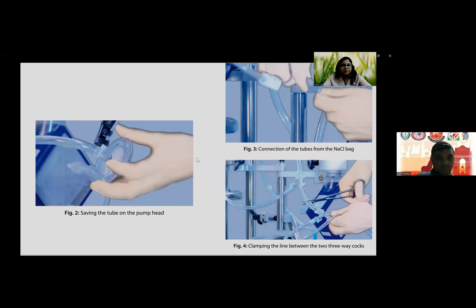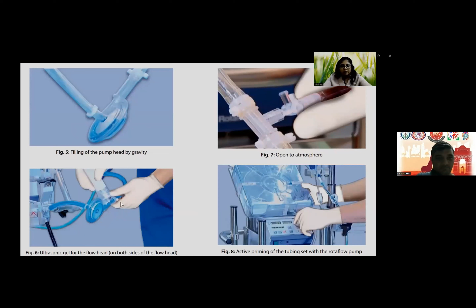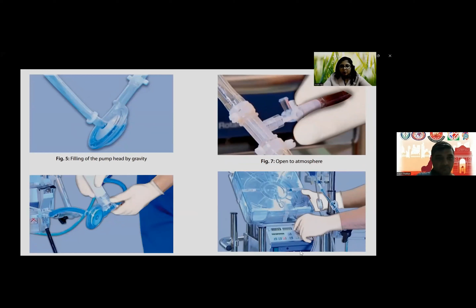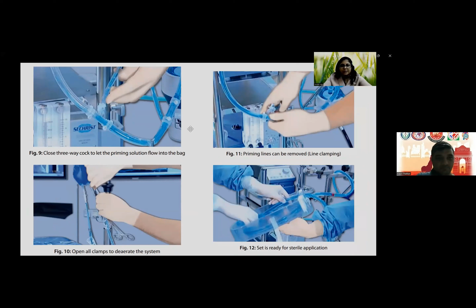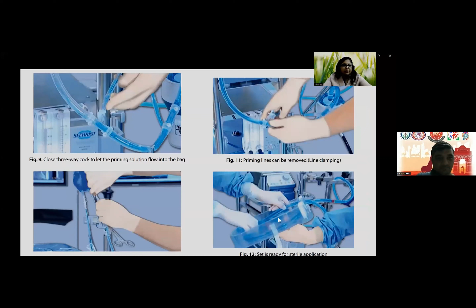Then with the help of gravity, you fill the pump, right? And then you apply the ultrasonic gel to the flow head on both sides of the flow head, and then you open to the atmosphere so that the de-airing is done, and then you actively prime the tubing set with the Rotaflow pump. We will understand all this in detail by seeing the video also, right? And then you close the three-way cock to let the priming solution flow inside the bag, right? You open all the clamps to de-air the system. Then you prime the lines, and the priming lines can be removed. You clamp the lines, and then the set is ready for sterile application.